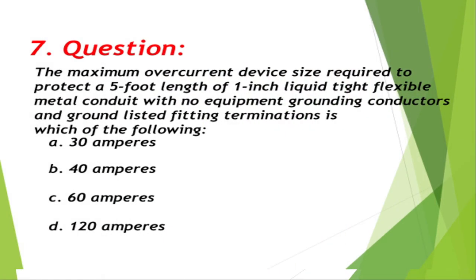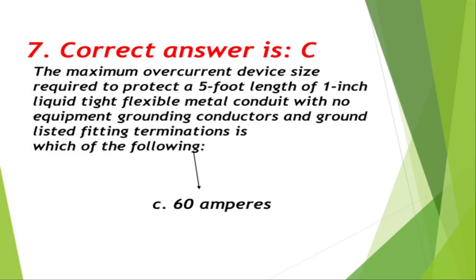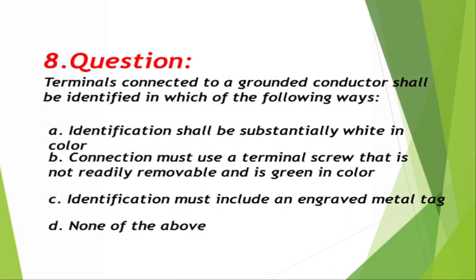Question number 7: The maximum overcurrent device size required to protect a five-foot length of one-inch liquid-tight flexible metal conduit with no equipment grounding conductors and grounded listed fitting terminations is: A. 30 amperes, B. 40 amperes, C. 60 amperes, D. 120 amperes. Correct answer is C, 60 amperes.